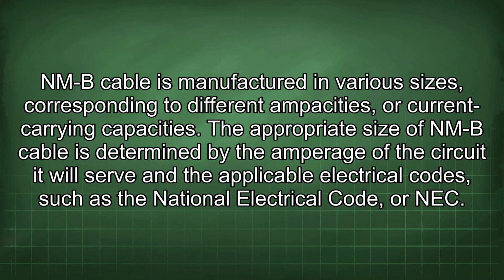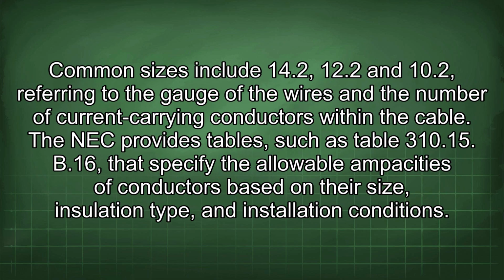NMB cable is manufactured in various sizes corresponding to different ampacities, or current carrying capacities. The appropriate size of NMB cable is determined by the amperage of the circuit it will serve and the applicable electrical codes such as the National Electrical Code, or NEC. Common sizes include 14/2, 12/2 and 10/2, referring to the gauge of the wires and the number of current carrying conductors within the cable. The NEC provides tables, such as Table 310.15(B)(16), that specify the allowable ampacities of conductors based on their size, insulation type, and installation conditions.